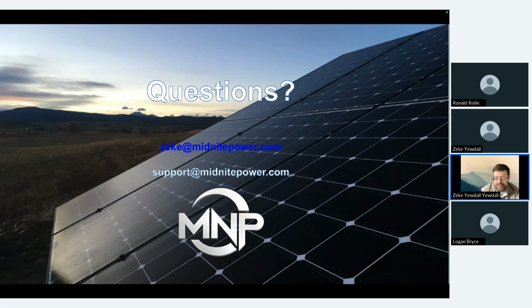And that's just where you want to look at your settings and think, I want to make sure this battery gets to 100% at least once a week, just to make sure my state of charge is being accurately measured and I don't run into a situation where my battery's actually discharged a bit more than my state of charge is indicating. But you don't need as much for the balancing, but for the state of charge drifting, you still need to. So I would say, yes, it's more important for the PF5s, but it's kind of like an additional issue, and it's still important for all lithium batteries to do that regularly, just to keep that BMS in sync with reality.